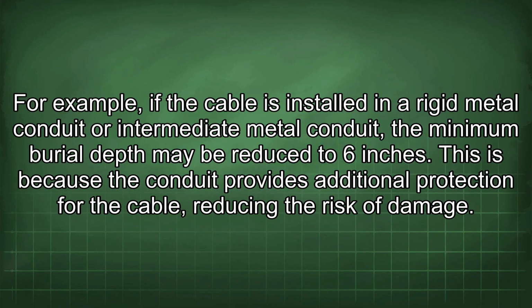For example, if the cable is installed in a rigid metal conduit or intermediate metal conduit, the minimum burial depth may be reduced to 6 inches. This is because the conduit provides additional protection for the cable, reducing the risk of damage.